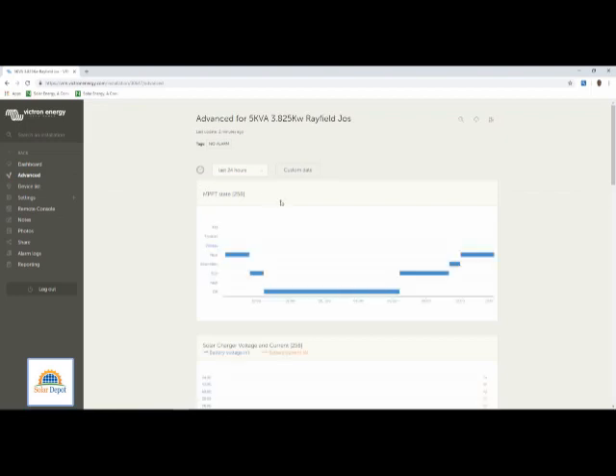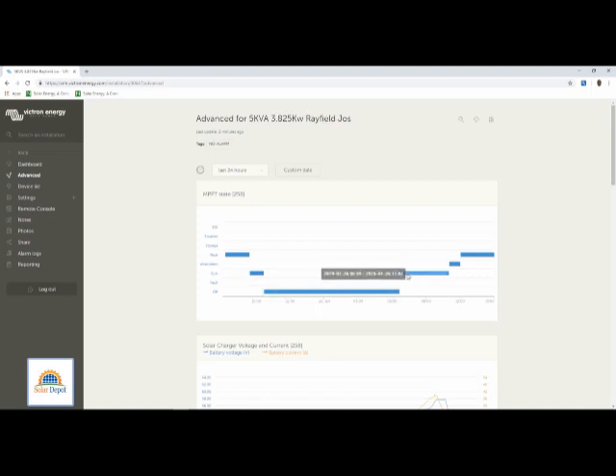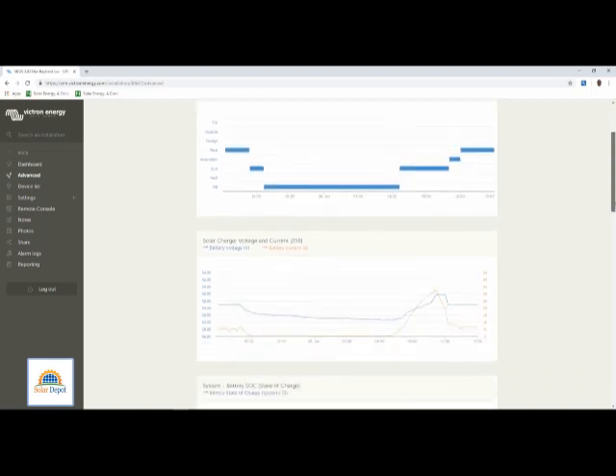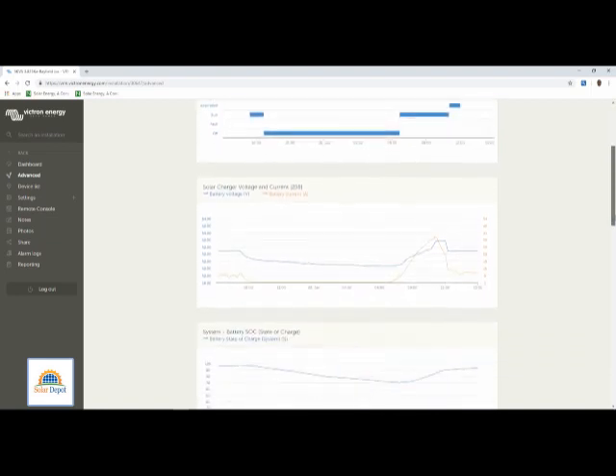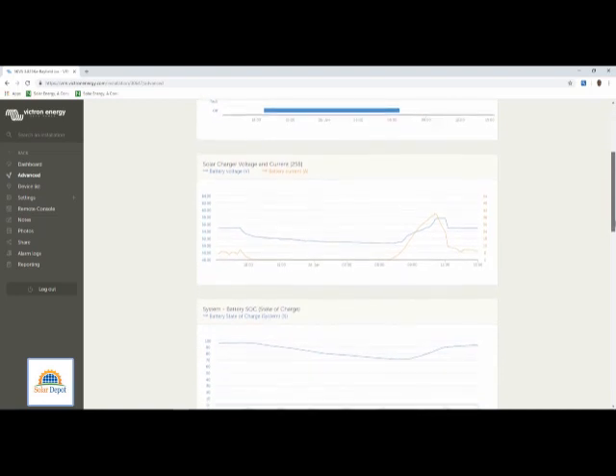By clicking on the advanced button, we'll see the other parameters like the activities of the MPPT to charge the batteries. From bulk, they started at 6:39 AM to 11:02 AM meaning that polycrystalline panels have early start-ups just like monocrystalline panels. Absorption started at 11:02 and ended at 12:02. Float started at 12:02 till date.